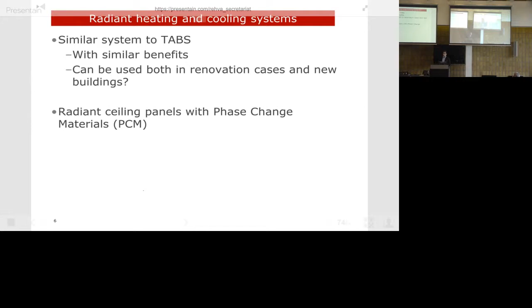One option is radiant ceiling panels with phase change materials. What are phase change materials? They could be organic or inorganic materials, and they mainly work through the utilization of latent heat, which is the part we benefit from most. They could be used passively or actively—actively meaning you control their charging or discharging behavior. They allow thermal mass enhancement and temperature control of indoor spaces, which means you can manage the cooling load.